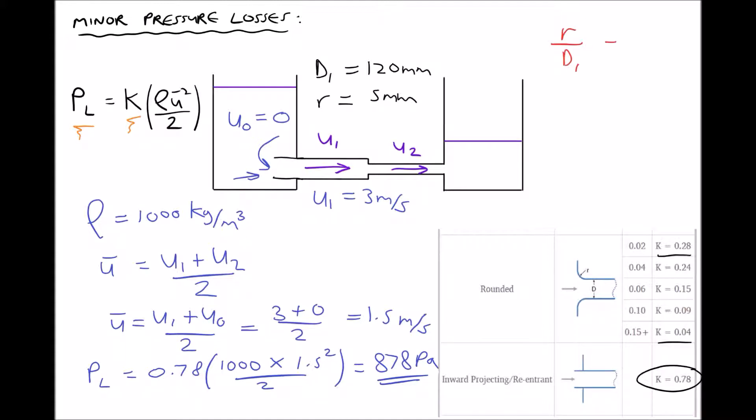So the first thing that we need to do is find the value of our ratio radius over diameter. In this case it's the diameter of pipe 1. Providing we use the same units for both the radius and the diameter, it doesn't really matter whether we work in meters or millimeters. So we'll work in millimeters and we get 5 over 120, giving us a value of r over d equal to 0.042. When we reference the r over d column here, we can see that our value of 0.042 rounded to two decimal places equals 0.04. Therefore we're going to use a K value equal to 0.24.